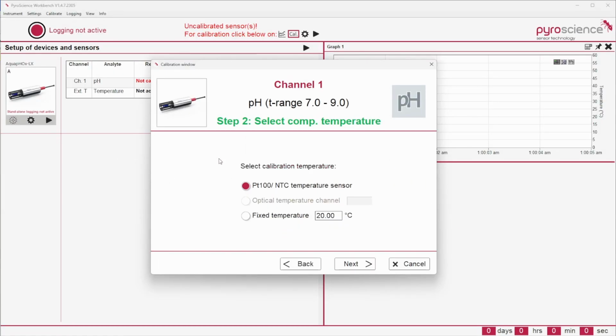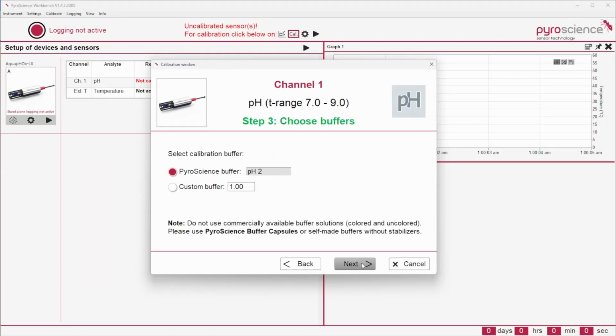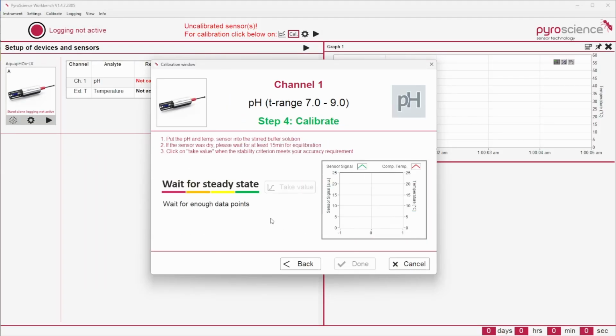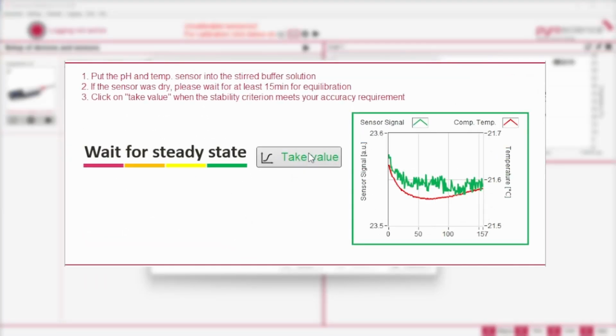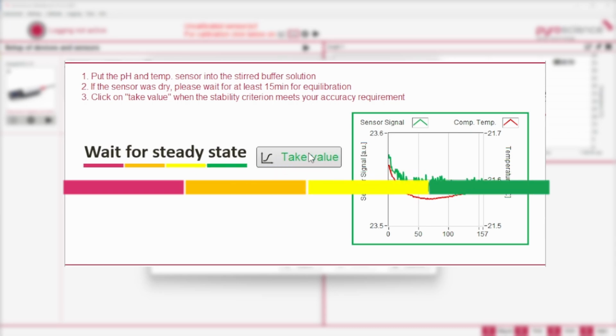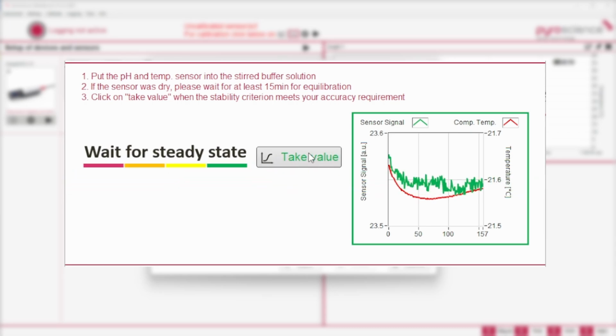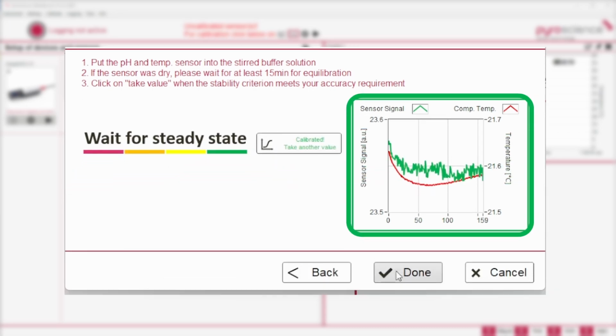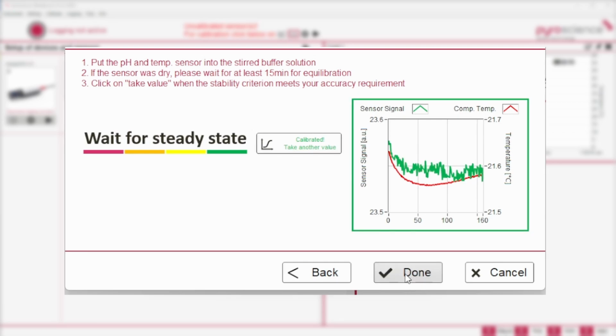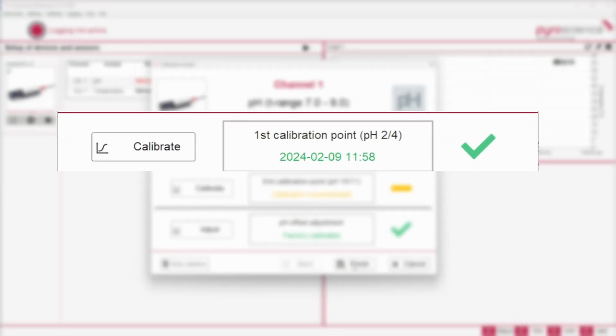Enter all required parameters of the used temperature sensor. The software will automatically start recording for the calibration. Click Take Value when the readings of the optical sensor and temperature probe are stable in the respective calibration standard and the Take Value button is enabled. With increasing stability of the sensor signal, the color will change from red to orange to yellow to green. For the best calibration results, wait until the Take Value button and the frame of the graph have turned green. Click on Done to complete the calibration. A successful calibration is indicated in green, showing the latest calibration date.